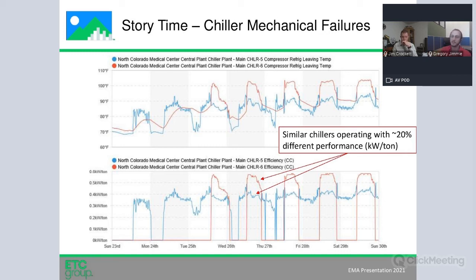So what happens is that when we started to manually manipulate the way the capacity control works, more modern chillers will use VFDs, inlet guide vanes, and variable geometry diffusers. And those are all ways in which the compressor can modulate up and down as load varies in your system. So without going too detailed into that, we basically manually manipulated how much capacity one of the chillers was able to do. And when we were trying to actually increase its capacity, it was decreasing. So something wasn't quite right.